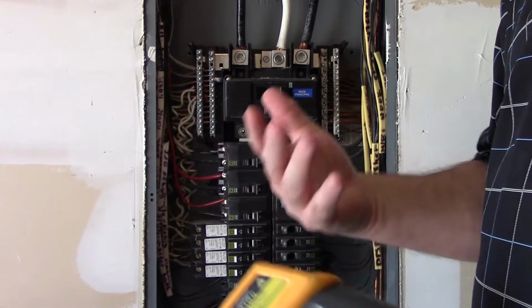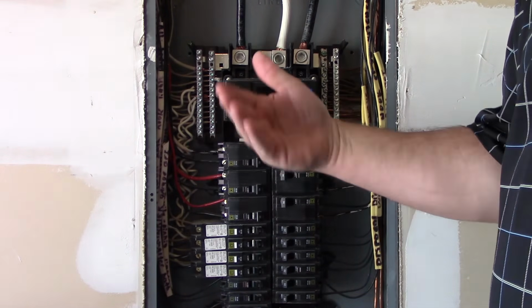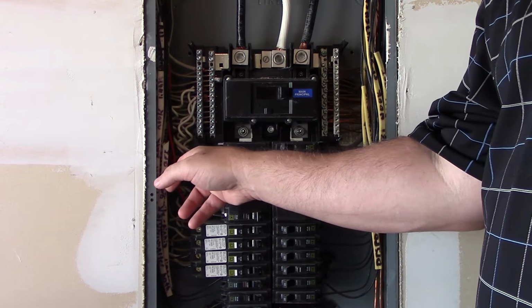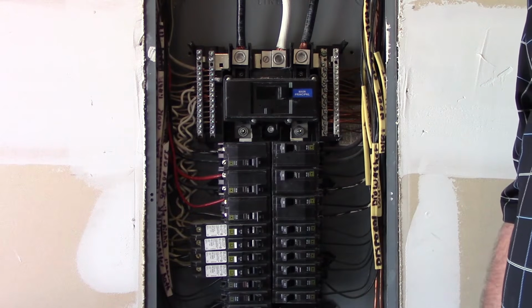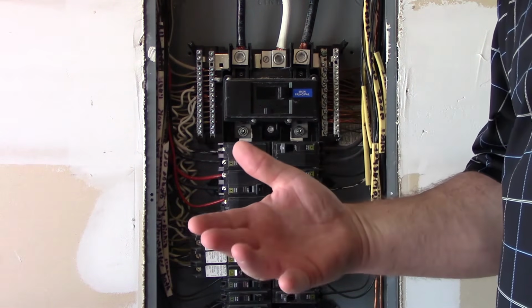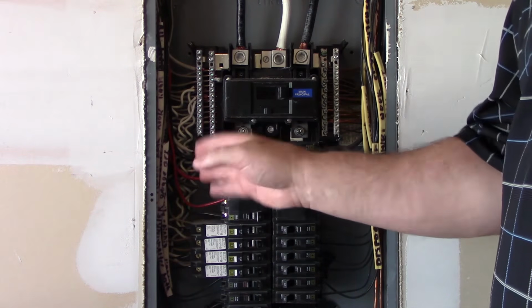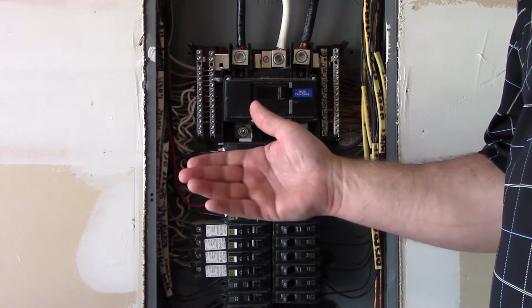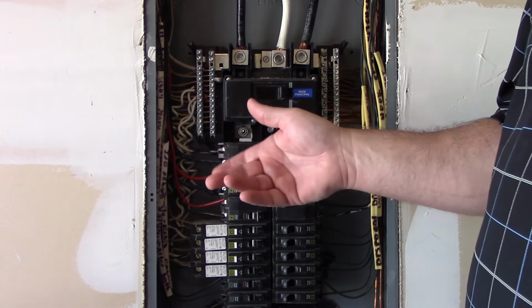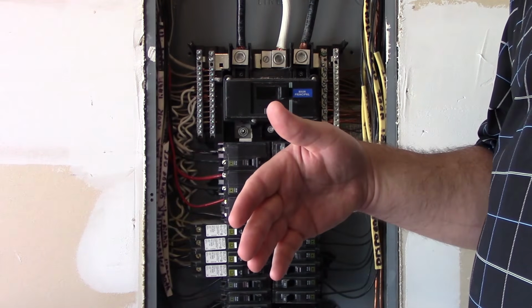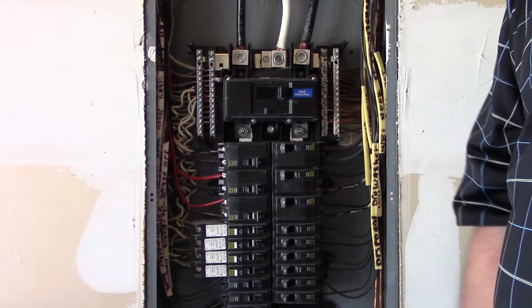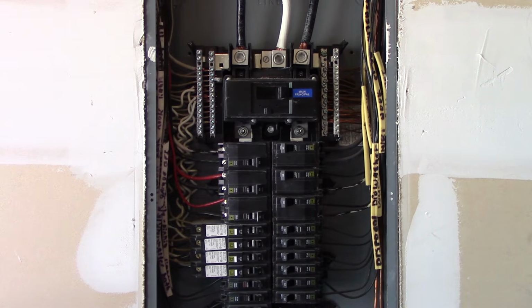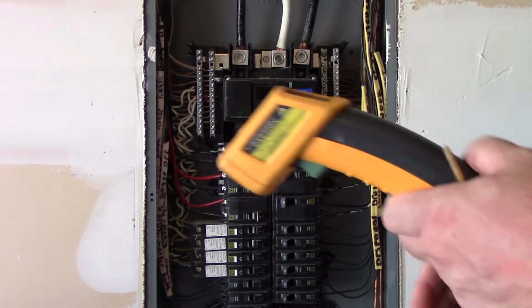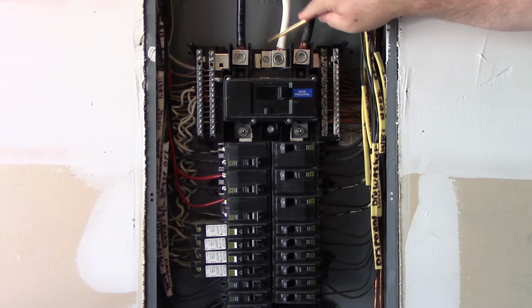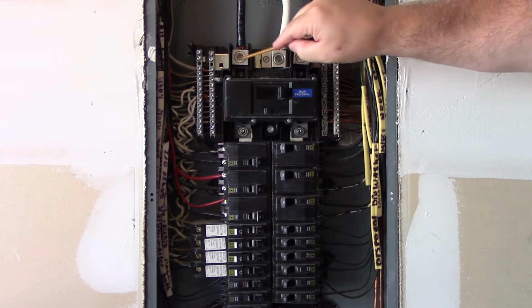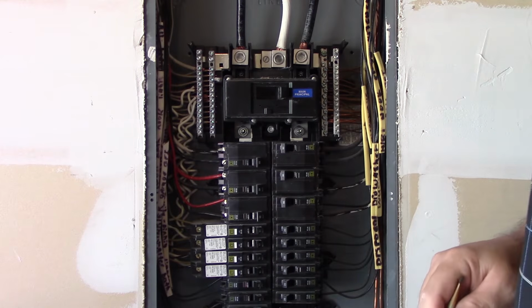Again, if there's any load going on, they might warm up and be a little warmer. But you're looking for drastic differences, understanding that under a load condition the terminals are going to heat up. We have 90 degree rated insulation, that's 90 degrees C, or 194 degrees Fahrenheit, for the overall rating. We know that this is non-metallic sheathed cable, so we are limited to the 60 degree rating in accordance with 334.80 of the National Electrical Code. The ampacity values are going to be in accordance with 310.15(B)(16) in the 60 degree column. That's what you're dealing with when you're dealing with non-metallic sheathed cable. The service cables up here are actually at 75 degrees for ampacity based on this terminal, so in our case we used 310.15(B)(7) for that application.